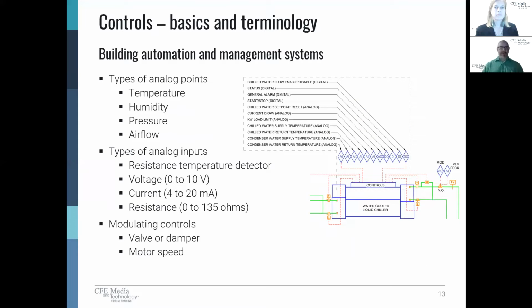Now, points are a digital representation of what's actually happening in the system. I can have real points or virtual points. And a real point is going to be hardwired. It's important that engineers understand and define this very early on because it's going to affect the cost of the system. Hardwired points have cabling. They have to wire that cable. They have to be secured. And what if that point is 1,000 feet away? Obviously, there's a cost to that. And engineers have to consider what points they physically need.